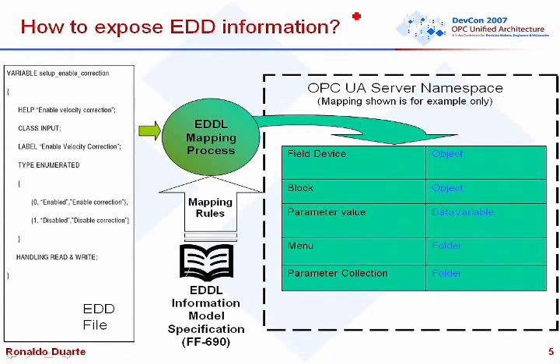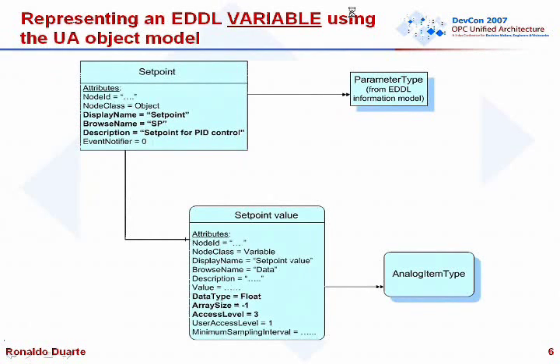Here is an example of how a parameter from a function block inside the device is represented — specifically a set point parameter. The information model says to create a variable to store the parameter value. The set point value is an OPC UA variable that holds the parameter value retrieved from the fieldbus network. The attributes shown in bold are the ones coming straight from the EDD; the server defines the other attributes based on OPC UA specifications.